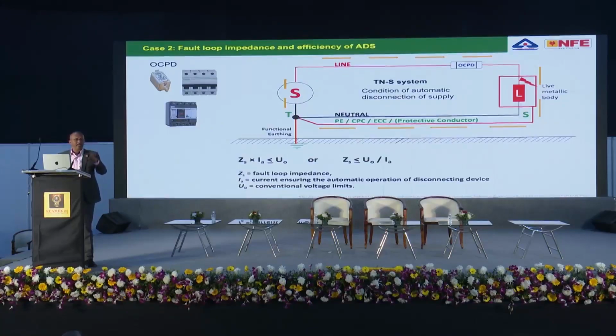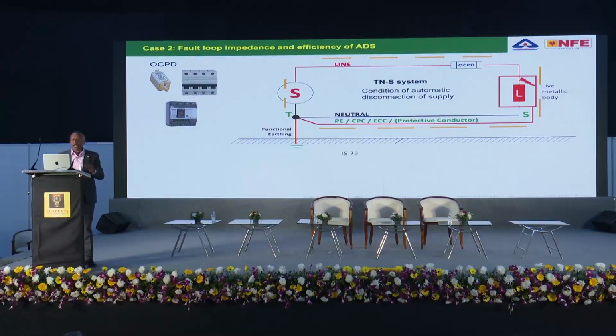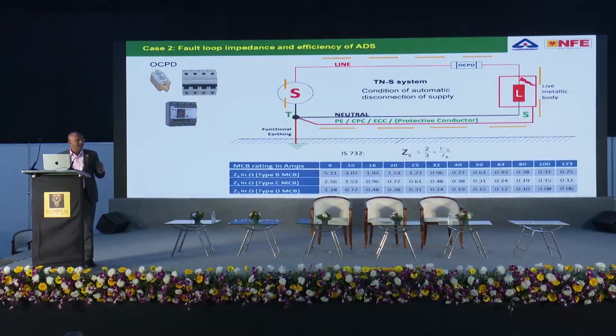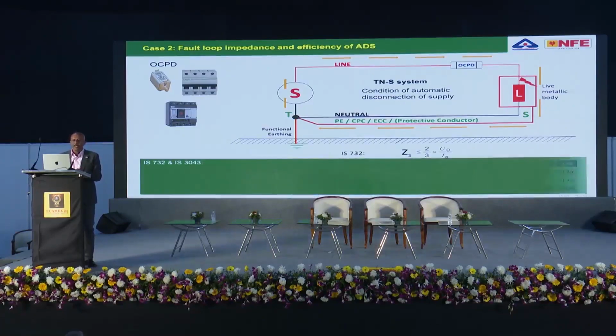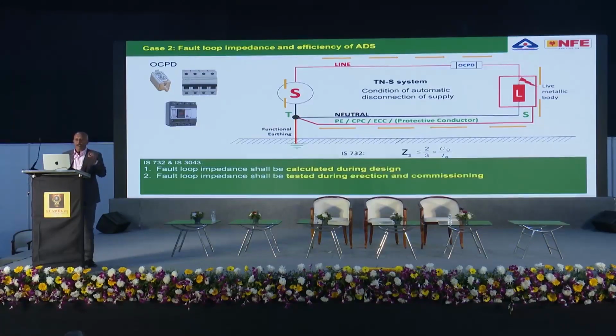Our electrical installation should be made in such a way that during a fault of negligible impedance, the minimum current flowing through that MCB should be more than 630 amps. That is what it is. So the calculations are given here. In IS 732, we have also included a table which talks about the impedances. If you look in detail, fault loop impedance shall be calculated during design, it has to be verified during erection, it has to be tested during audits, and so on.